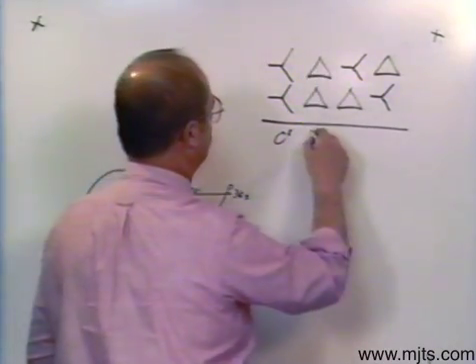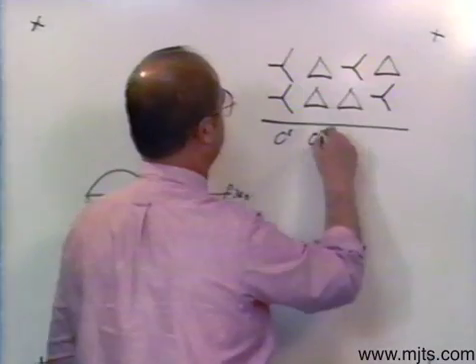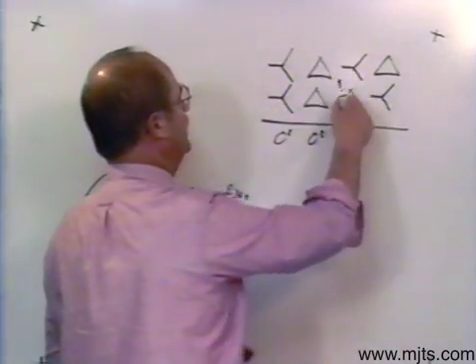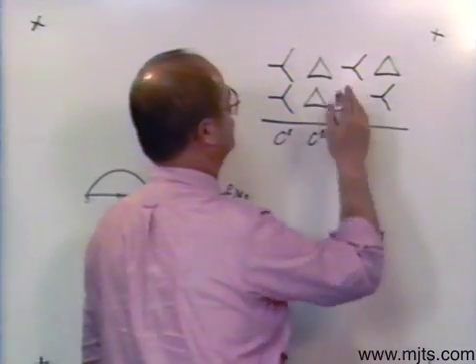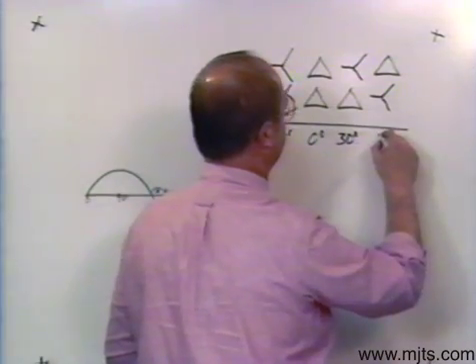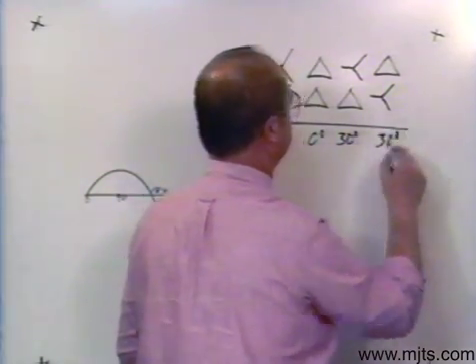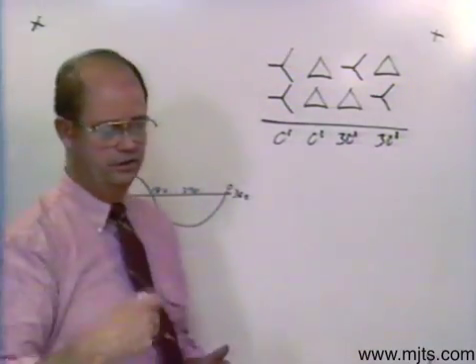On the Delta-Delta, I can have a zero degree. On the Y-Delta, my least possible displacement is 30 degrees. And same way with the Delta-Y, my least possible displacement is 30 degrees.